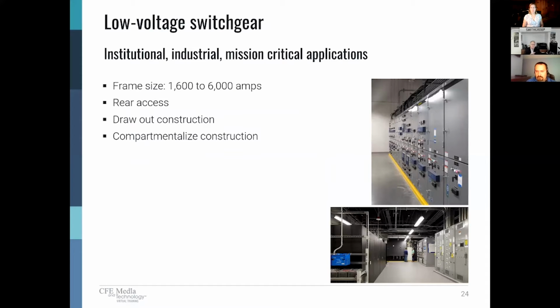So let's talk about switchgear. Switchgear and switchboard are often used interchangeably. There are whole presentations on these types of topics. But switchgear is typically going to be draw-out construction. It's going to require rear access to do terminations of the cables. And they have compartmentalized construction. And again, like the switchboards, they go up to 6000 amps as well. The 6000 amp breakers do require additional internal cooling fans, but those are available. And when you're planning your room in the early phases of design, you've got to take all that into consideration. Next.